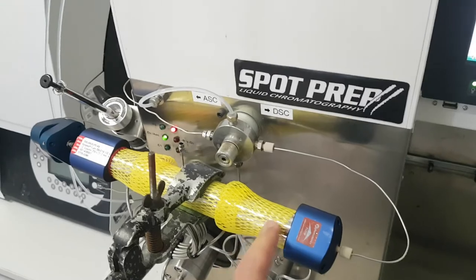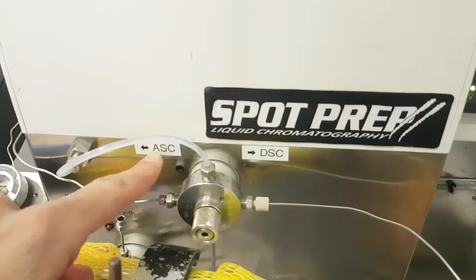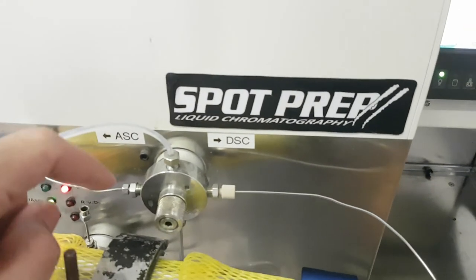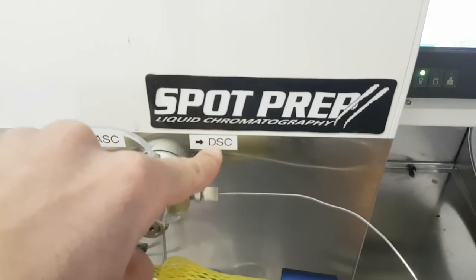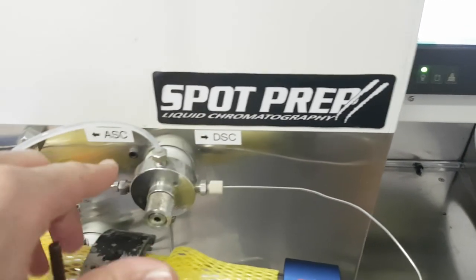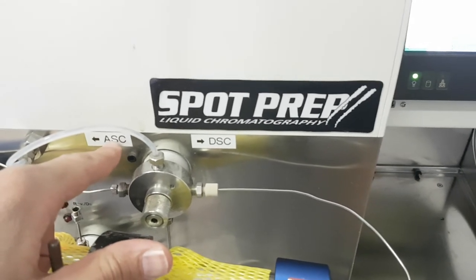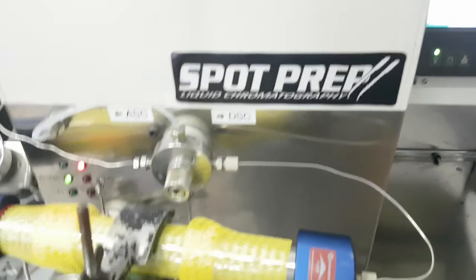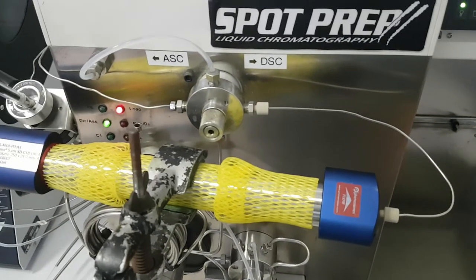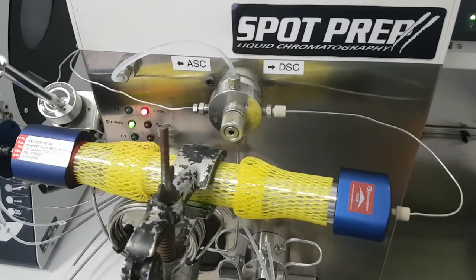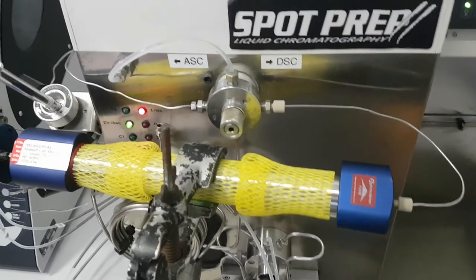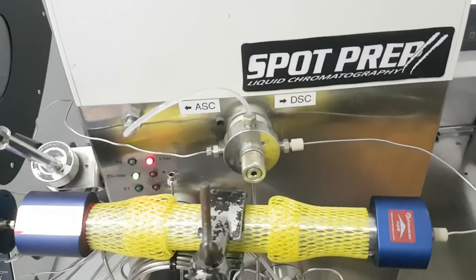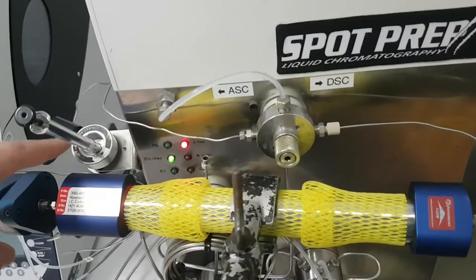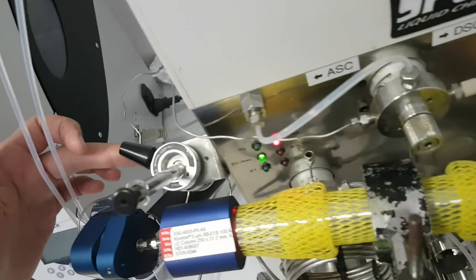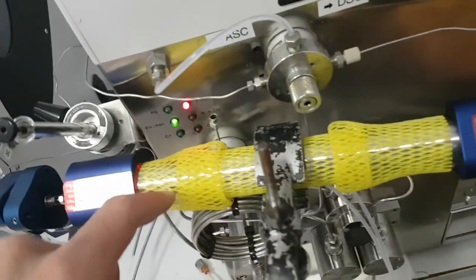Moreover, if your sample is not totally dissolved, you need to filter it. You need to filter your sample using a syringe and a filter here, because if you still have some powder or some precipitate, it might get stuck in the column and is not practical. It will destroy your column. So this is the mode that we are using. This is the inverse. So you need to pay attention usually to whether you are using the ASC or the DSC, so the separation, which direction it goes from where to where. Because when we inject here, we inject from here, and it goes in that direction.